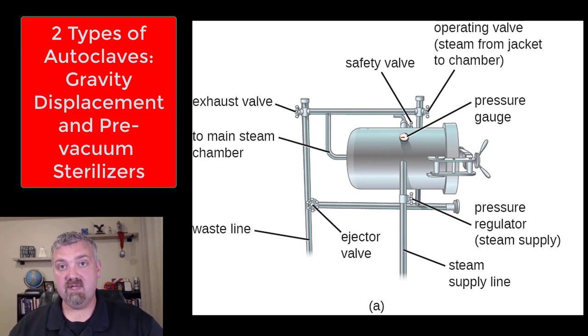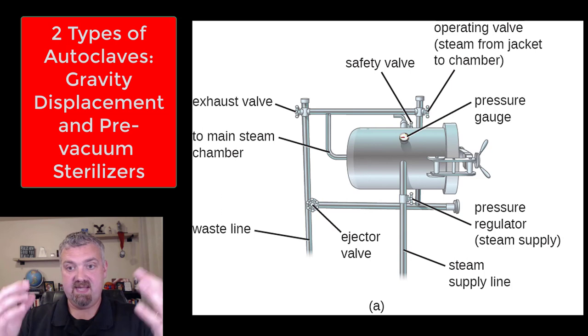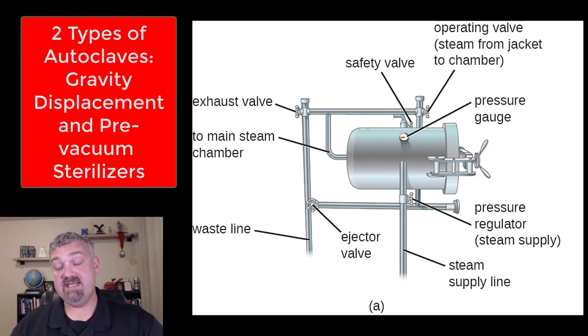There's the gravity displacement autoclave, which is the one that we use in our lab, which means that steam is going to enter into this chamber. And as steam enters into the chamber it's going to force the air out. So that's why it's called gravity displacement. The air is going to be forced down and out of the chamber. Once all the air is gone, then basically the container will be sealed and now it's full of pressurized steam.